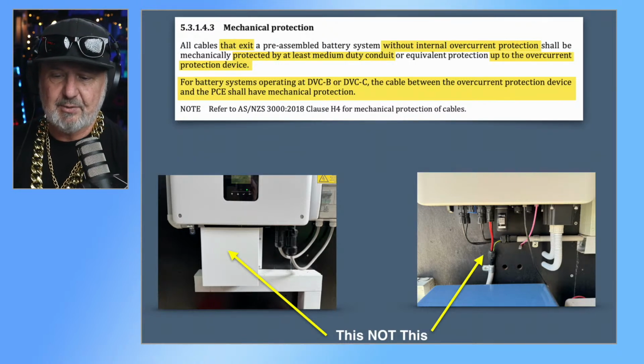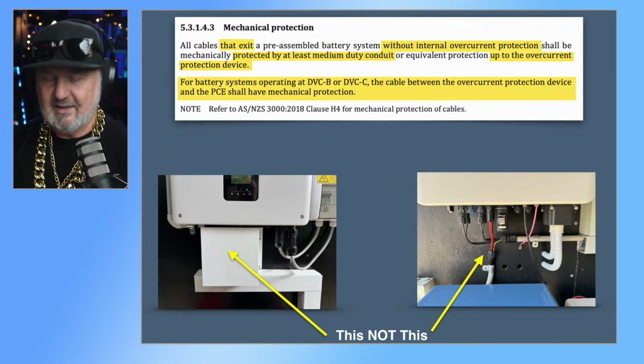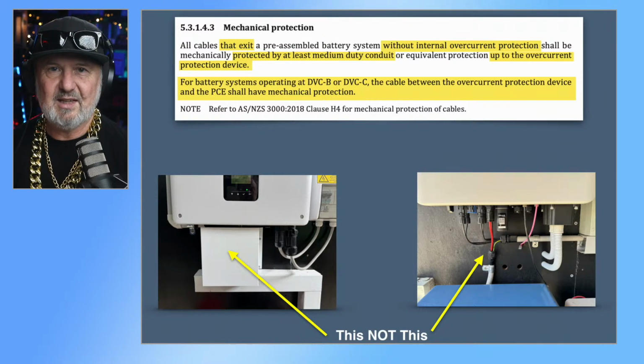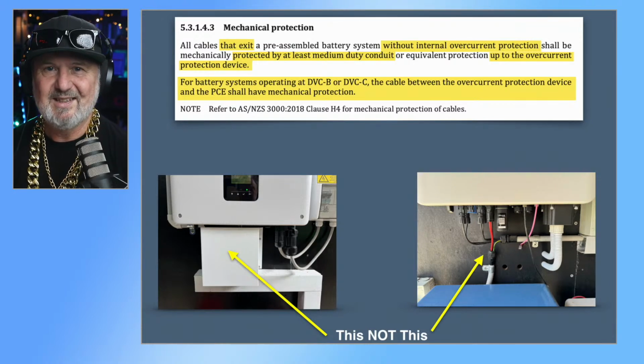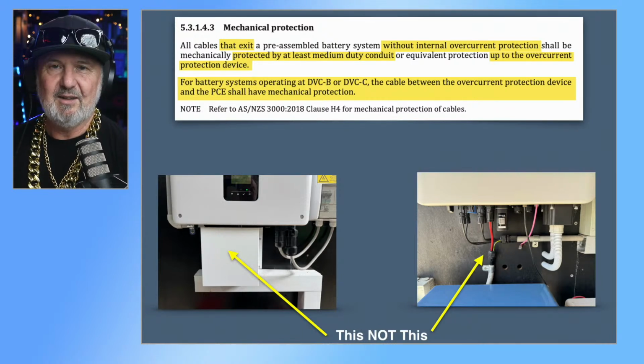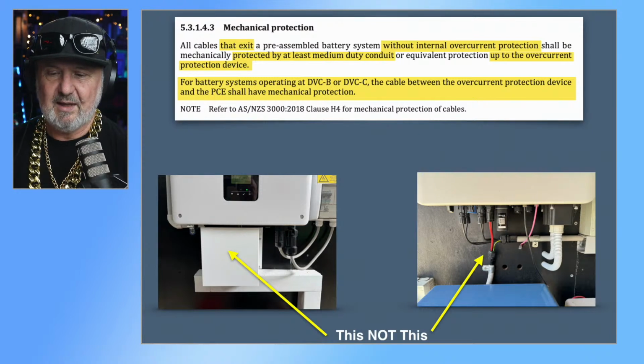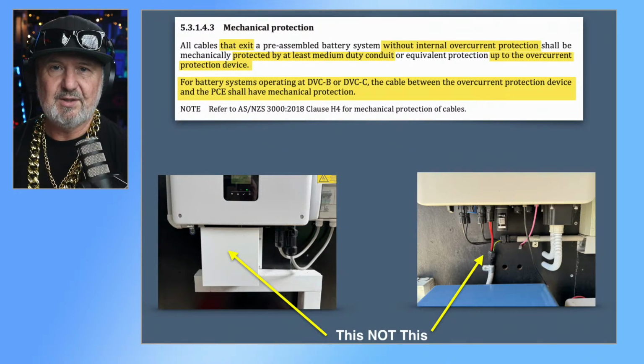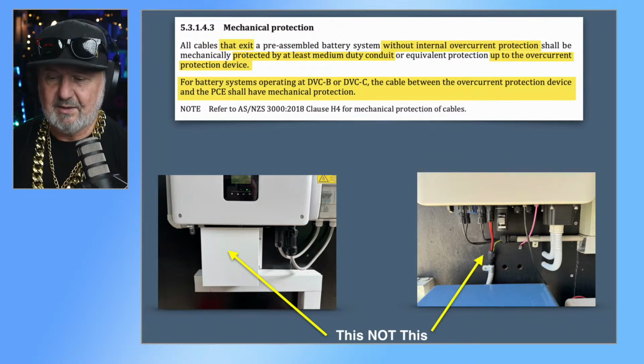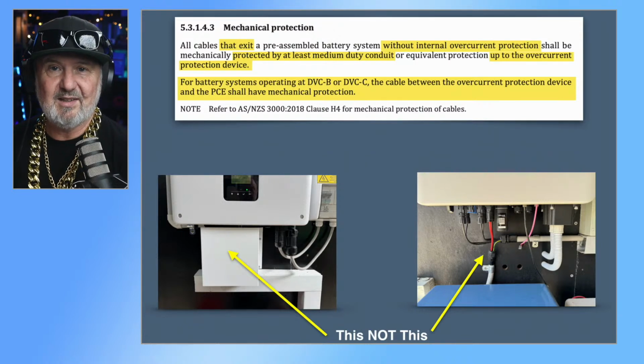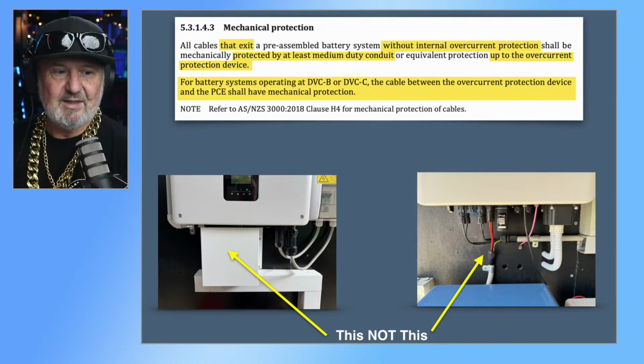Shepsy, yes, I was using the 90-degree table because there isn't a 110. There's a 120 and a 90. But if you can make it with 90, you can definitely make it with 110-degree rated cable. So yeah, you need to follow the work method in 3008. I should probably do a Toolbox Tech Talk on 3008 because it's actually quite a complicated little standard. I used to think you just go to Table 4 because that's what I do, batteries. No, it's not that simple. You've got to look at all the D ratings, not just within the means of installation, but also what the protection device is, whether it's a circuit breaker or a fuse, and there's D ratings based on that as well. So you've got to consider a few more factors. But anyway, that's a topic for another Toolbox Tech Talk, how to read 3008.